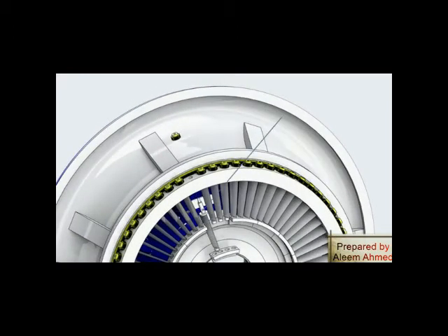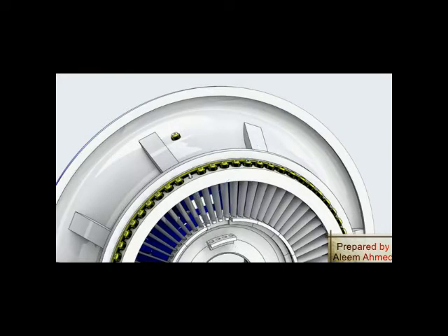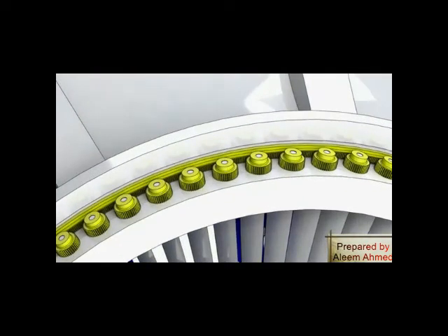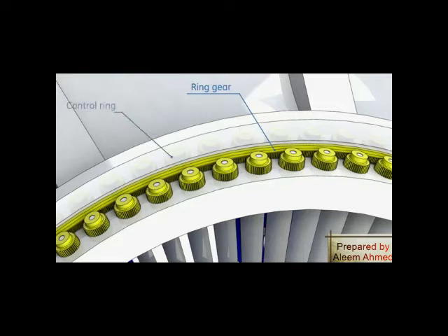Each blade stem is inserted into a hole machined on the inlet casing, and each four of them are supported from below by one inner segment. A pinion gear is installed to each blade stem and is keyed into position. These pinions are rotated by a ring gear which is assembled to the control ring.